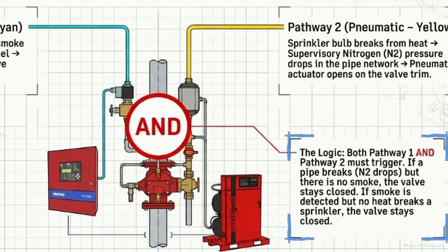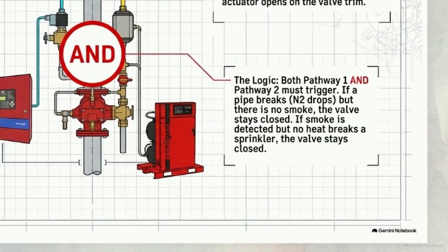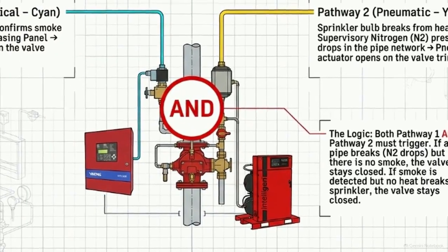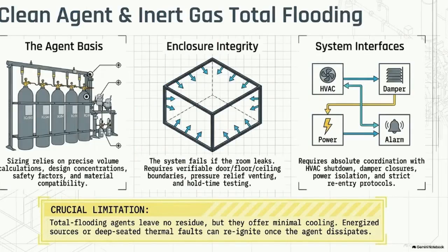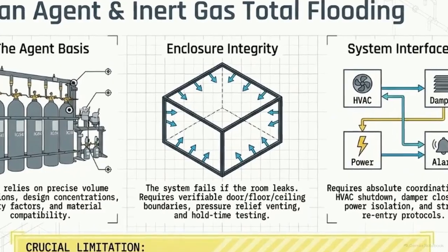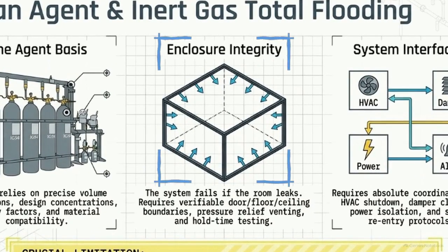If smoke is detected but there is no heat to break a sprinkler, the valve stays closed. If a pipe is damaged but there is no smoke, the valve stays closed. Both conditions must trigger together. Total flooding clean agents are often preferred for electrical rooms to avoid liquid damage, but they carry a crucial limitation noted here. These systems rely on perfect room enclosure integrity to maintain the required gas concentration. A leaking door seal causes the system to fail.